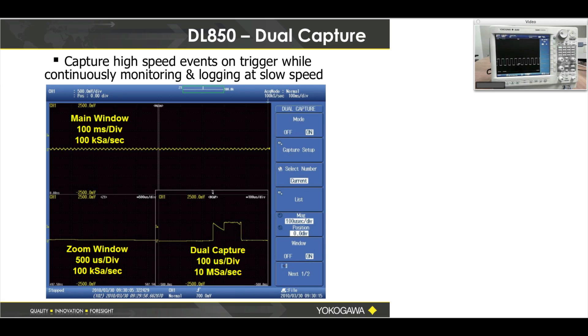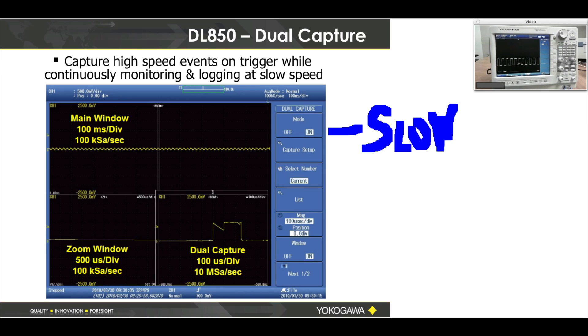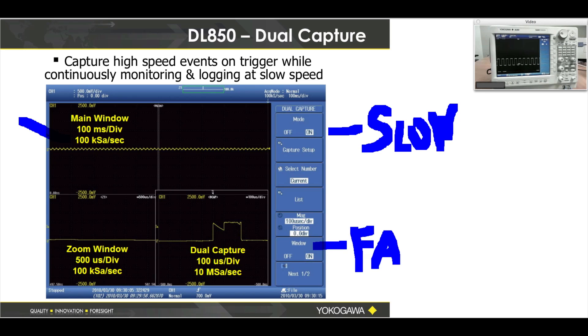In your main window you have a slow data rate — you may be sampling at 100 kilo-samples per second. You set up a trigger, and as soon as that trigger condition is met, the instrument will then sample at a much faster sample rate. That waveform gets saved into a different place in your binary file.